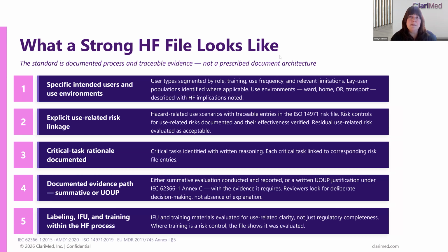Whereas if people are familiar with how it works for the FDA, that is a separate and standalone human factors file with some linkages back to a use-related risk assessment. 62366 and the MDR expect that very robust link back to 14971.